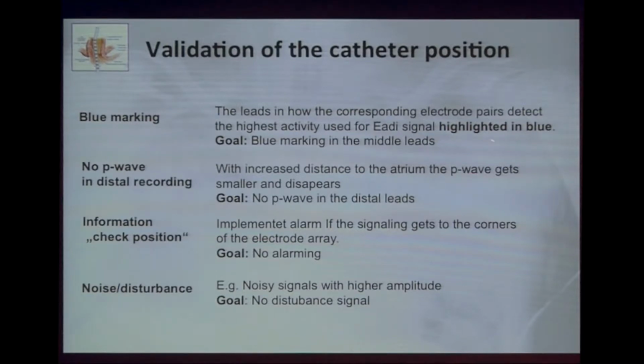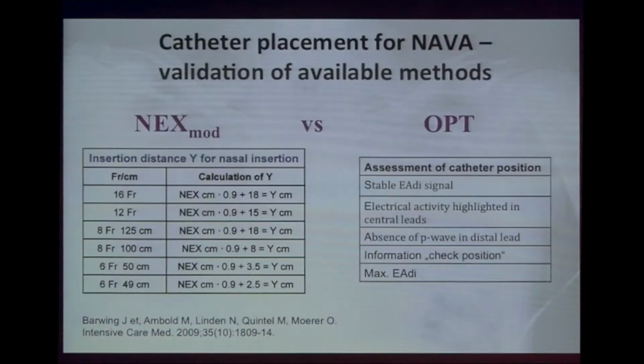The blue marking is a highlighted electrical signal where there's the highest activity, used to create the final Eadi signal. Then we go for the p-wave, I already mentioned that. We also have further information from the ventilator, check information, check the positioning as an alarm that of course shouldn't be there, and of course we also have to look for noise and disturbances which can be seen in this catheter placement window.